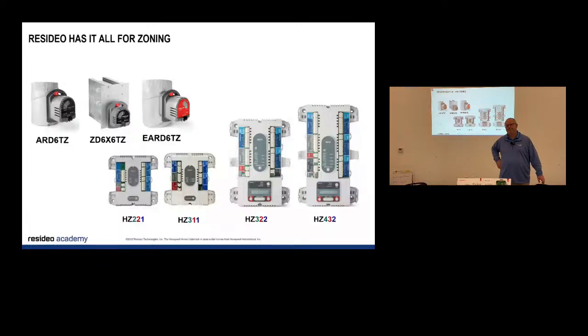Well, so if I heard this right, you're saying 60% into the smallest zone, right? Yep, so let's say I had a 3-zone. Would it be like in the biggest? I mean, why is it that way? No, because if the 2 biggest zones shut, I still have a ton of CFM from that system going into the smallest zone. I see what you're saying. Follow me? It's not taking as much. Correct. I'm not too worried if I got a bigger zone, because if the small zone and a medium zone shut, more than likely, if I'm at least 60%, that small zone is not pushing that. Bingo. The worst case scenario, right?